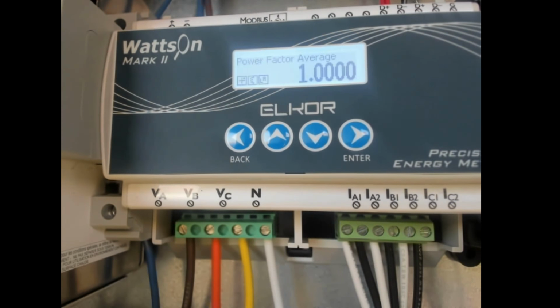It could be. I mean, honestly, I wouldn't even look at the voltage rating. I would look at the size of the plant and make a call there. If you're measuring a point of interconnection that's greater than 1 or 2 megawatts, you may want to consider giving the client an SEL 735, just because there's a lot more options and troubleshooting if the site requires any kind of power quality meter. The Elkor meter, it's a good option, and technically it can measure anything that the SEL 735 can, assuming it's the same form factor.